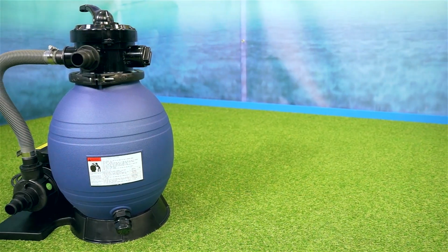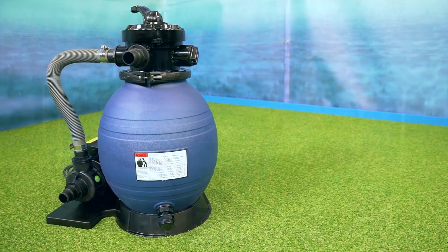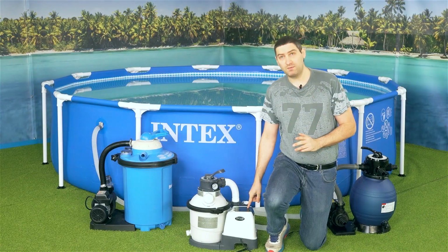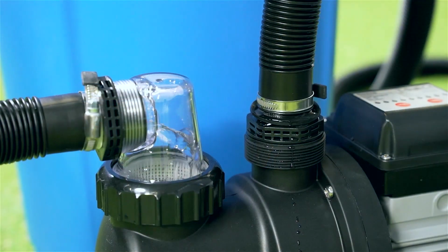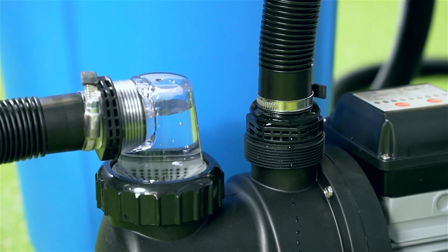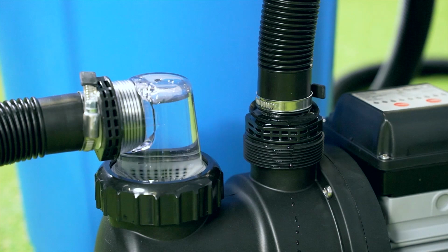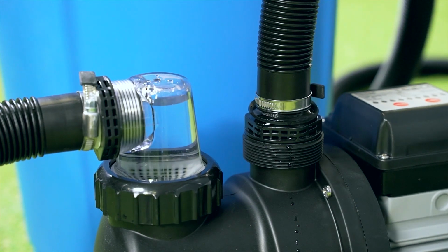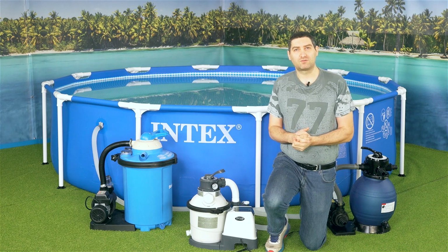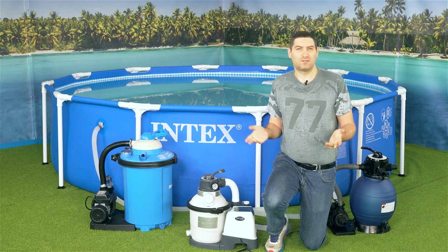And it is important that when you put the sand filter system into operation, there must always be water in the pump housing. This applies to all sand filter systems. If there is no water in it, because you didn't let the water run in before or you didn't fill it with water, then the sand filter system just draws air, runs hot and then has total damage. And the manufacturer or retailer will then refuse you the warranty or guarantee.